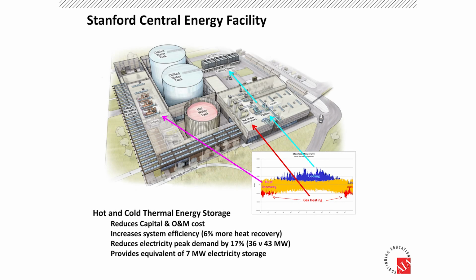Here's what the system looks like for our campus. It's been operational since 2015. The heat overlap shown in gold is handled by the three big heat pumps off to the left. For the cooling in summer, where we don't have a home for the heat, you can see for about 8 or 10 months of the year there's no red at the bottom of that gold. In summer, 100% of our heating needs have been met through our air conditioning.